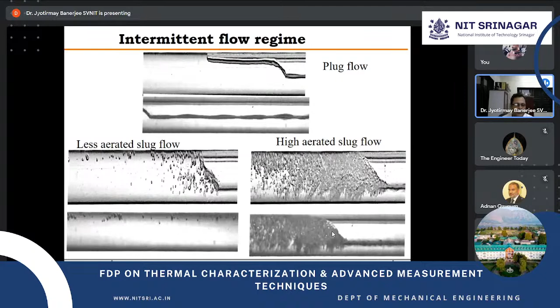Then the next regime is less aerated slug. Here you see the gas bubble and the liquid plug, but the liquid plug is full of small bubbles. These small bubbles will collide, collapse, and agglomerate, merging onto the wall at times, but it's still less harmful since the bubbles are fewer in number. But looking at the nose of the next bubble coming, there are a lot of gas bubbles and droplets—this is the most dangerous zone, called highly aerated slug flow. There is a gas bubble, liquid plugs, and many small bubbles, larger in number, which is highly catastrophic and causes erosion and corrosion to the pipe.